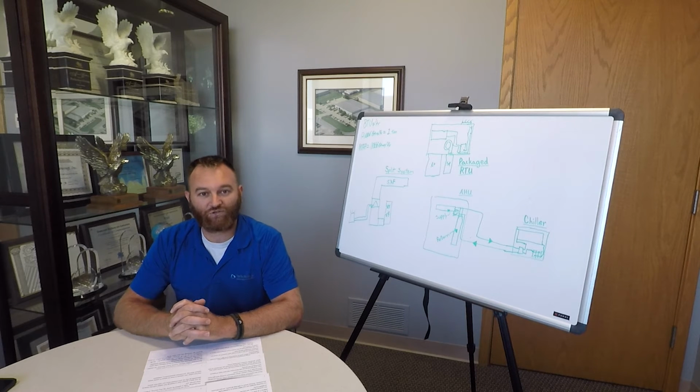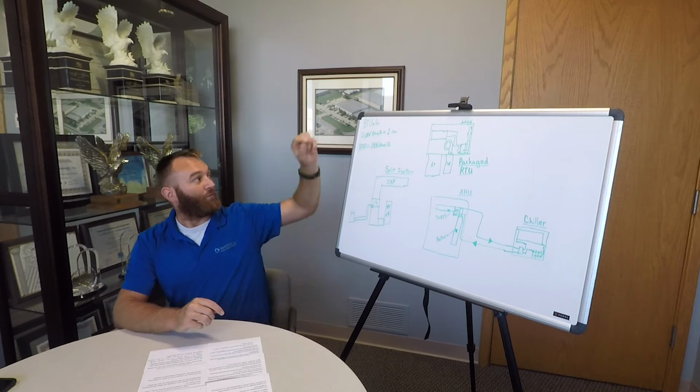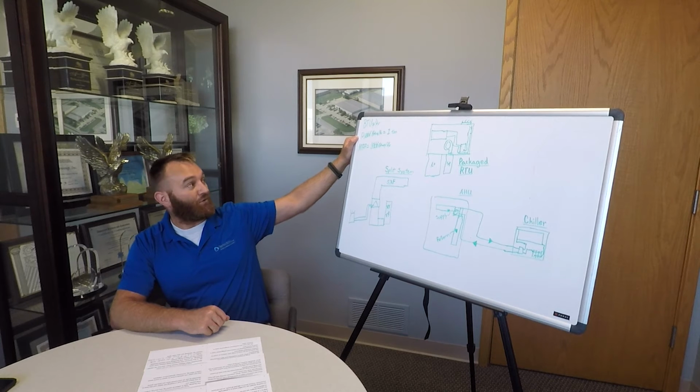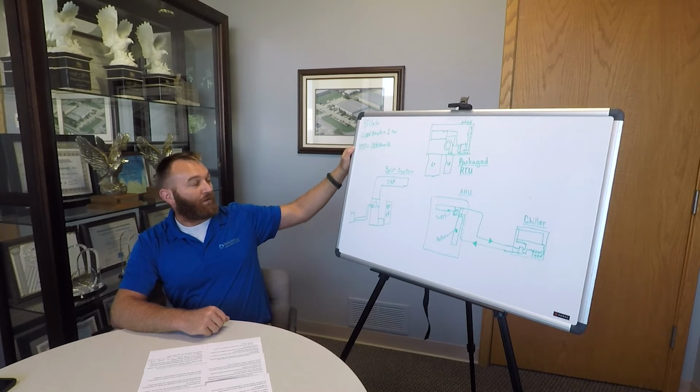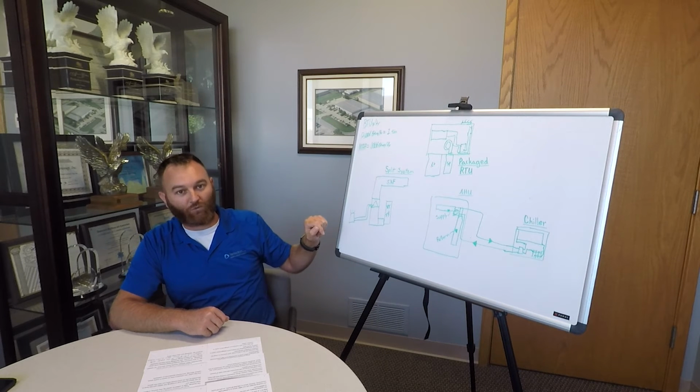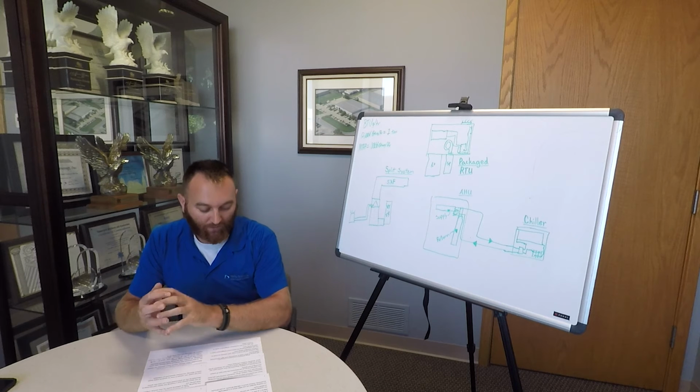First and foremost, we measure energy, heat loss or gain for HVAC systems in BTUs, or British thermal units. A BTU is the unit of heat required to raise 1 pound of water 1 degree Fahrenheit at an atmospheric pressure of 14.7 pounds per square inch. For cooling, we use tons, which is 12,000 BTUs per hour. For heating, we measure it in either MBH, which is 1,000 BTUs per hour increments, or just BTUs.